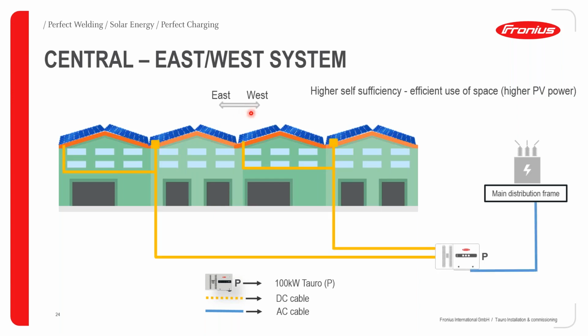What can happen as a design consideration is that all your strings or arrays that are oriented east are collected through DC combiner boxes and fed into one inverter. Then all the arrays that are facing west are collected and fed into another separate inverter. And we are going to look at why this might be the case for some installations.